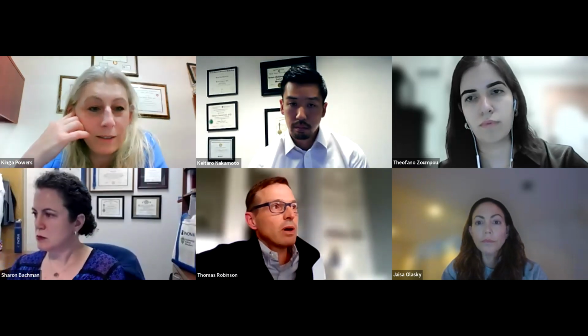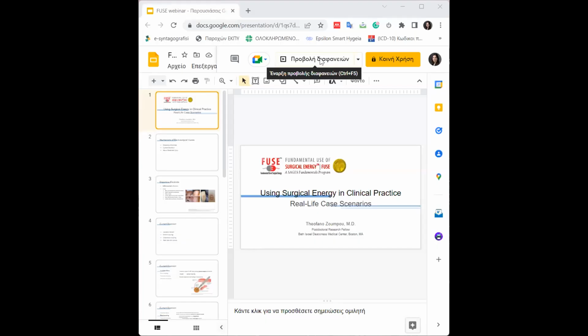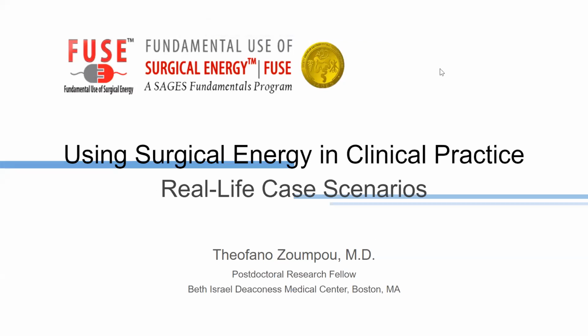So great, and I just want everybody to really put that in your brain, that coag delivers a really high voltage. Now, as we pull up this next set of slides, there are five things I have in mind that can change the clinical effect of the active electrode in the tissue. There are two on the generator: mode and power setting. The mode is cut versus coag—we've got a little bit in blend there too—and then your power setting, that's how many watts you set it at.